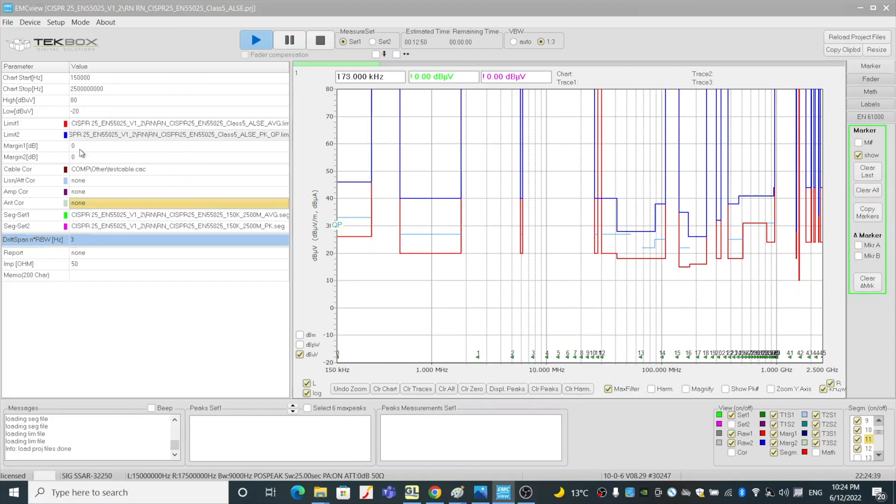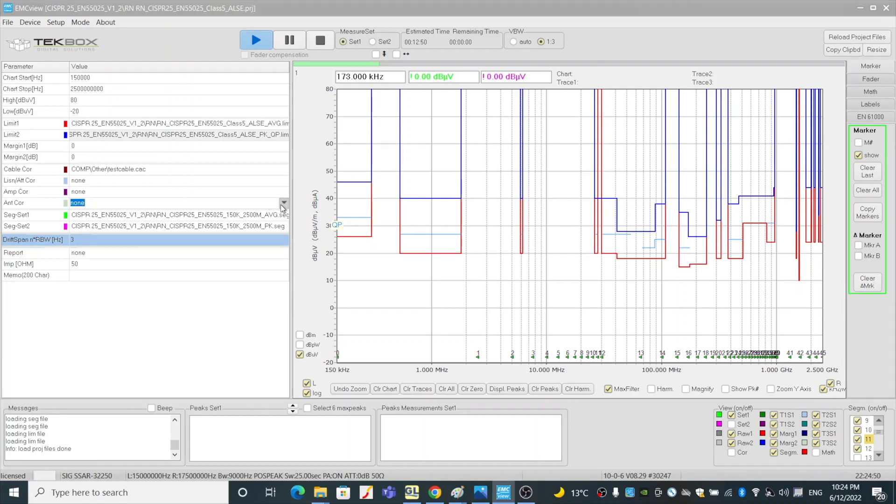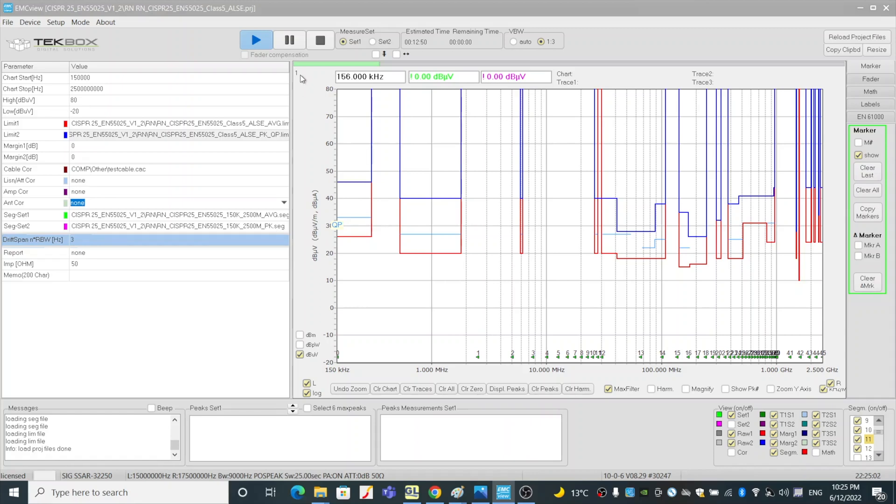Here there's really nothing to change. The antenna factor is important, but because the active monopole antenna we are using in this case has a very flat antenna factor and it's close to zero, there's no need to put any antenna factor in this case. Okay, so once the setup is set, let's click start to do the scanning.